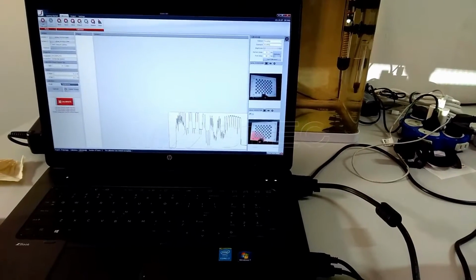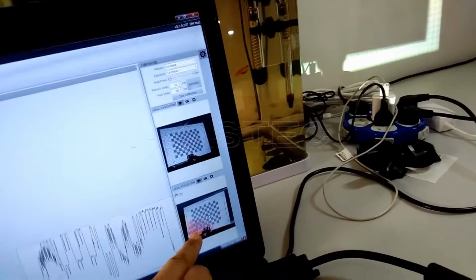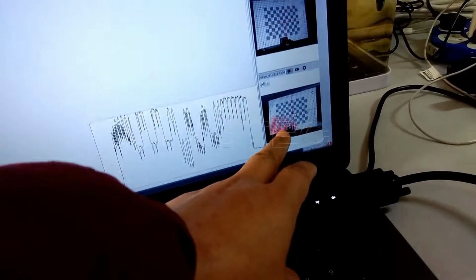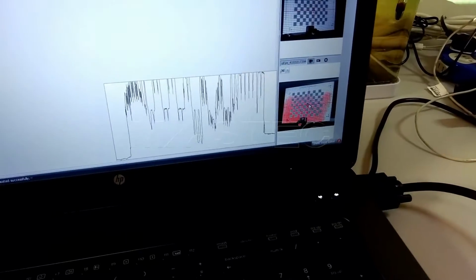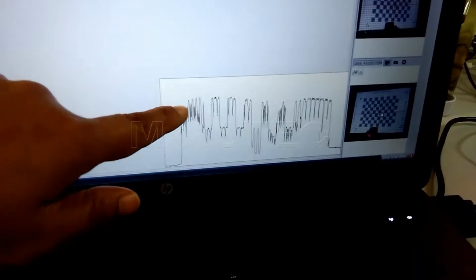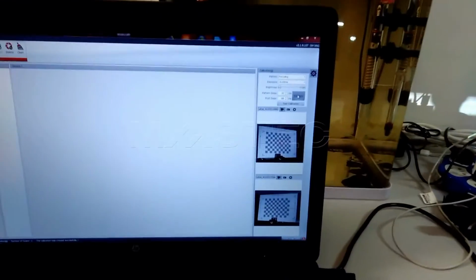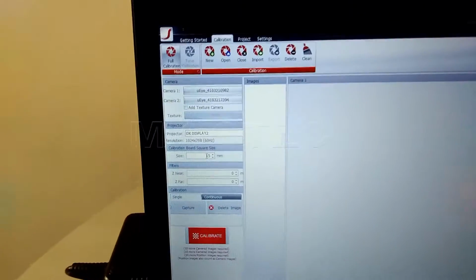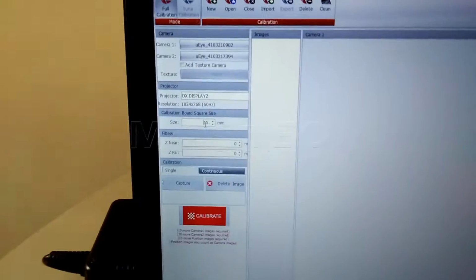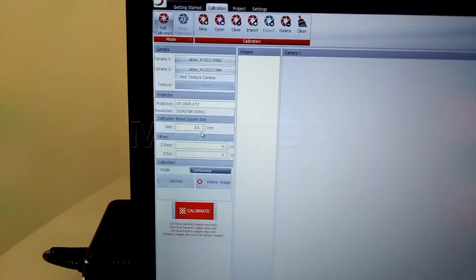For this image there is a red part, so we adjust only the aperture to remove it. Make this curve in the upper position. Then there is no red part now. Next, we press estimate. The value is about 30 to 70. Then we set the size of the calibration board in the software. The size must be the same as the actual calibration board.